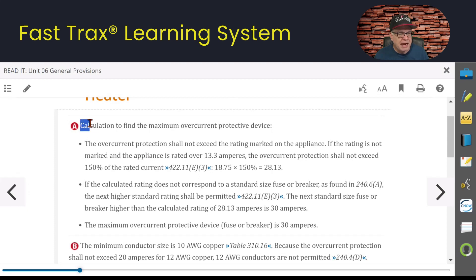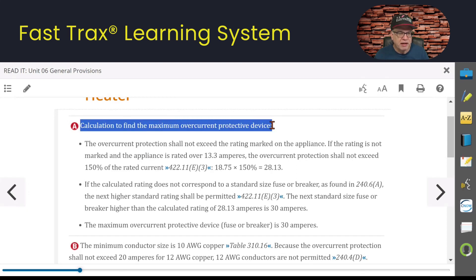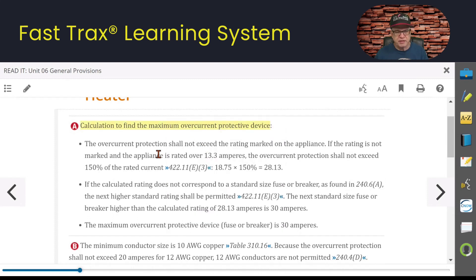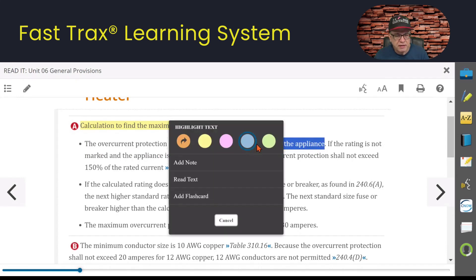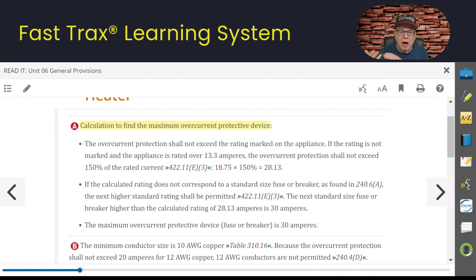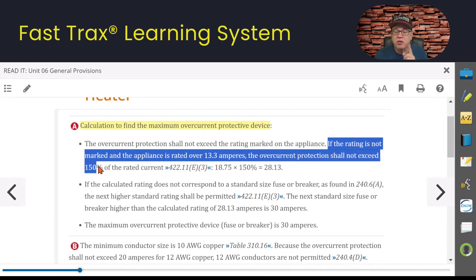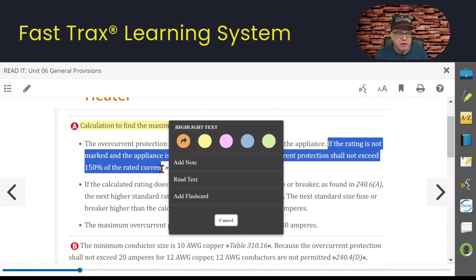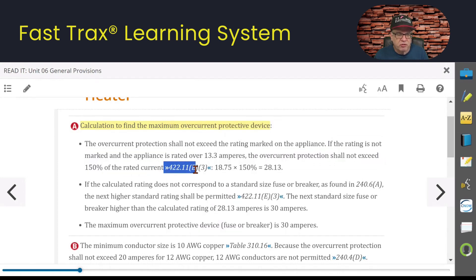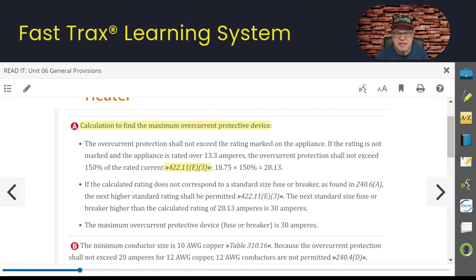Let's first calculate the maximum overcurrent protection device for this water heater. The overcurrent protection shall not exceed the rating marked on the appliance. Typically a water heater doesn't have any rating marked except for a wattage value. So it says if the rating is not marked and the appliance is rated over 13.3 amperes, the overcurrent protection shall not exceed 150% of the rated current. Where do we get all this from? We're going to look at 422.11(E)(3).